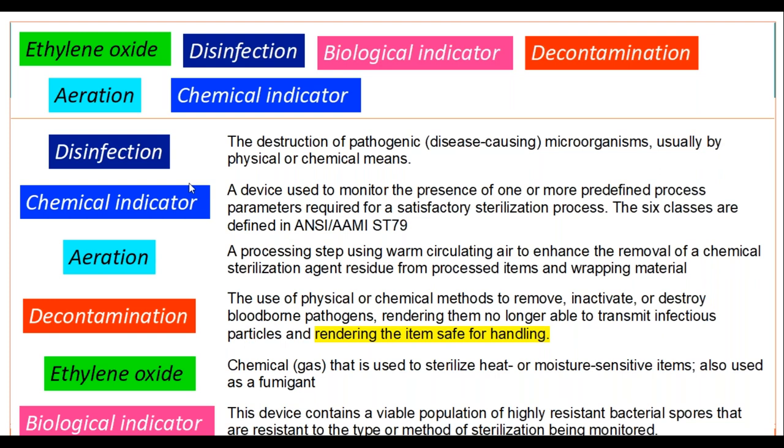Next, we have a device used to monitor the presence of one or more predefined process parameters required for a satisfactory sterilization process. There are six classes of chemical indicators defined in the ANSI/AAMI ST79. One key thing to remember: the word 'process parameters.' Chemical indicators look at parameters like temperature and humidity — don't confuse them with biological indicators.